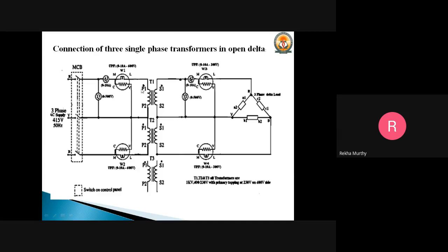You can see here the connection we have to do: part of the transformer connection is taken out, only T1 and T2 will exist, and on both sides it appears just like a two wattmeter method circuit. Whatever we have done on the primary side, the same needs to be followed on the secondary side. It is almost a two wattmeter method connection which we studied earlier, and the same procedure needs to be carried out. Even with two transformers we are able to carry some capacity and draw power. That is what you see in open delta.